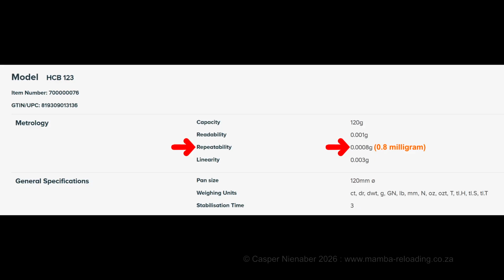Adam's specification is 0.8 milligram, while my own testing, which I'll share later, produced an even better result of 0.5 milligram. Linearity refers to the balance's ability to provide accurate readings across its entire weighing range, and is 3 milligrams. Overall, these specifications are extremely impressive, and as I will demonstrate later, my own tests matched, and in some cases exceeded, the manufacturer's claims. The balance features a practical 120 mm pan diameter.